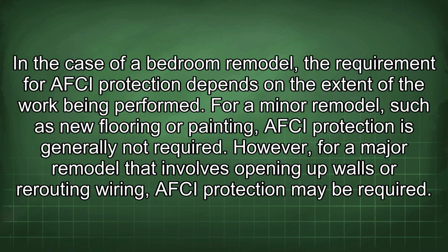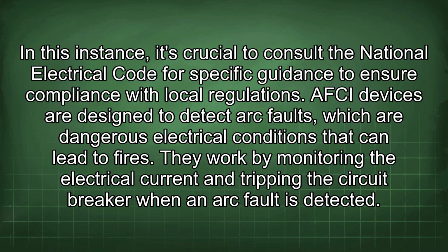In the case of a bedroom remodel, the requirement for AFCI protection depends on the extent of the work being performed. For a minor remodel such as new flooring or painting, AFCI protection is generally not required. However, for a major remodel that involves opening up walls or rerouting wiring, AFCI protection may be required. In this instance, it's crucial to consult the National Electrical Code for specific guidance to ensure compliance with local regulations.